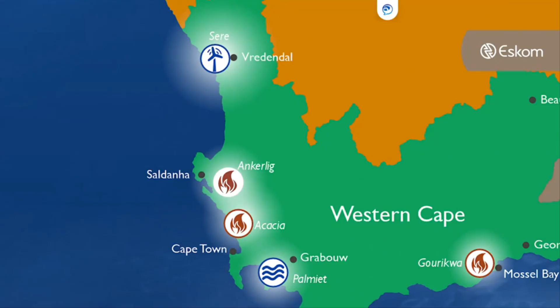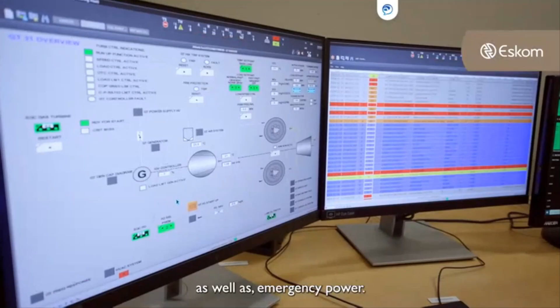We've also got the open cycle gas turbines. We've got Ankerlig situated in Cape Town, and Gourikwa situated in Mossel Bay. Those power stations run on diesel currently and have the ability to run on natural gas. The open cycle gas turbines are very critical when it comes to supporting the grid during times of peak as well as emergency power. Over the years, they have been used extensively to help prevent load shedding or further stages of load shedding, which has been very supportive to the grid. These units can also run, some of them in SCO mode, to help balance the voltage as well.